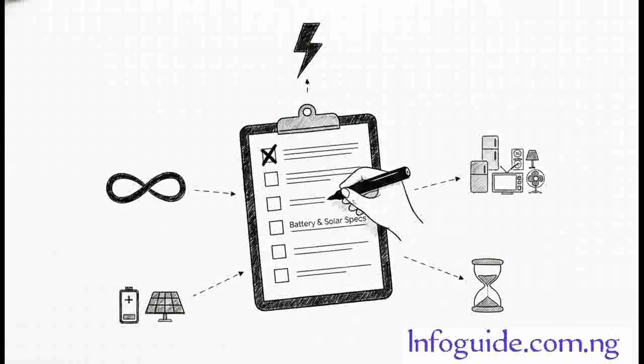Of course, simply doing that one quick math equation isn't the whole story. Figuring out the power factor is really just step one. To properly size an inverter so that your house doesn't suddenly go dark on you, a professional installer has to evaluate a whole checklist of critical variables well beyond just matching the top-line watts and kVA. We're talking surge current, continuous load, very specific battery and solar specs, load diversity, and your required backup time during an outage. It's a lot, right? Let's unpack a couple of the really crucial ones that almost always catch people by surprise.